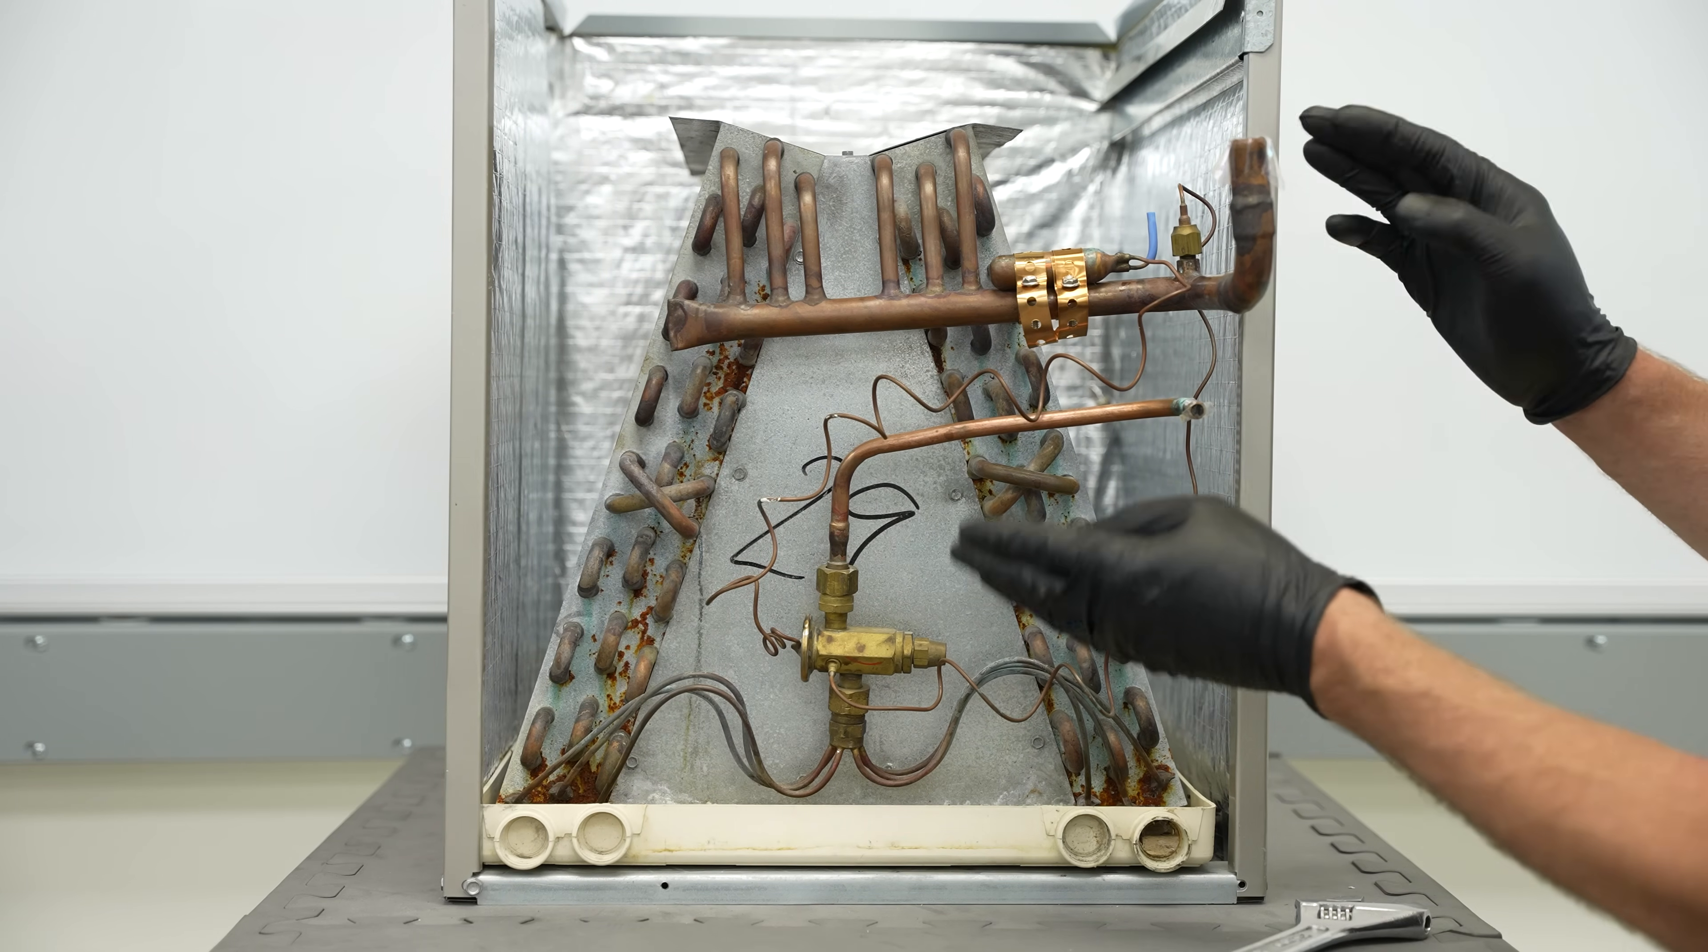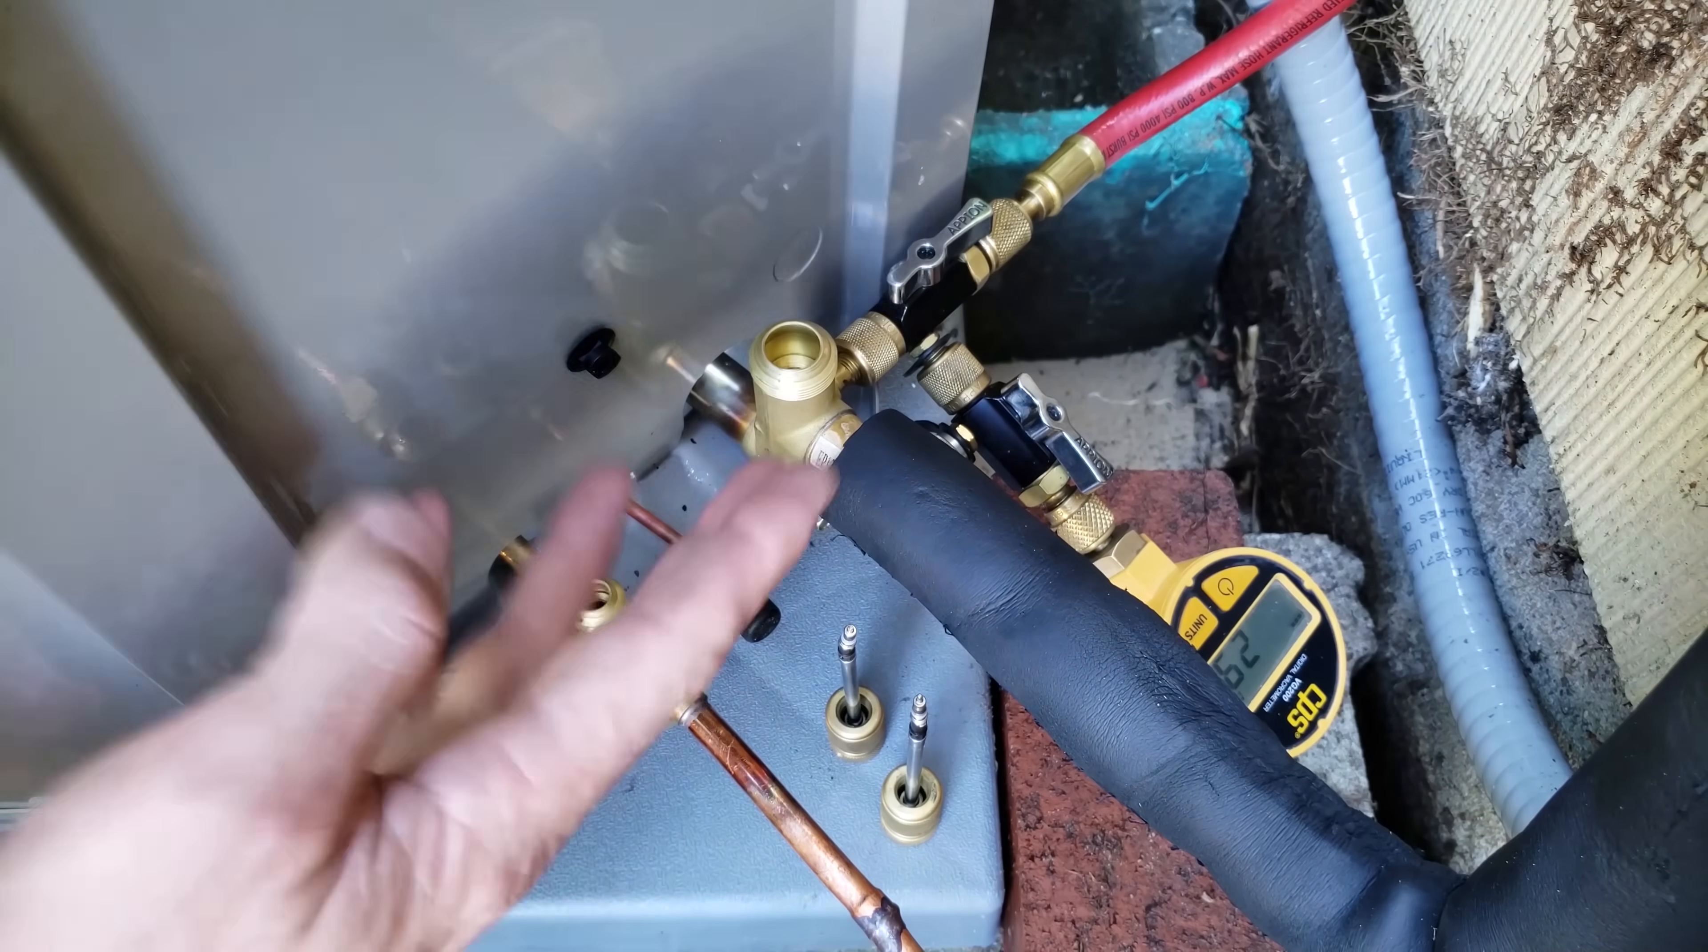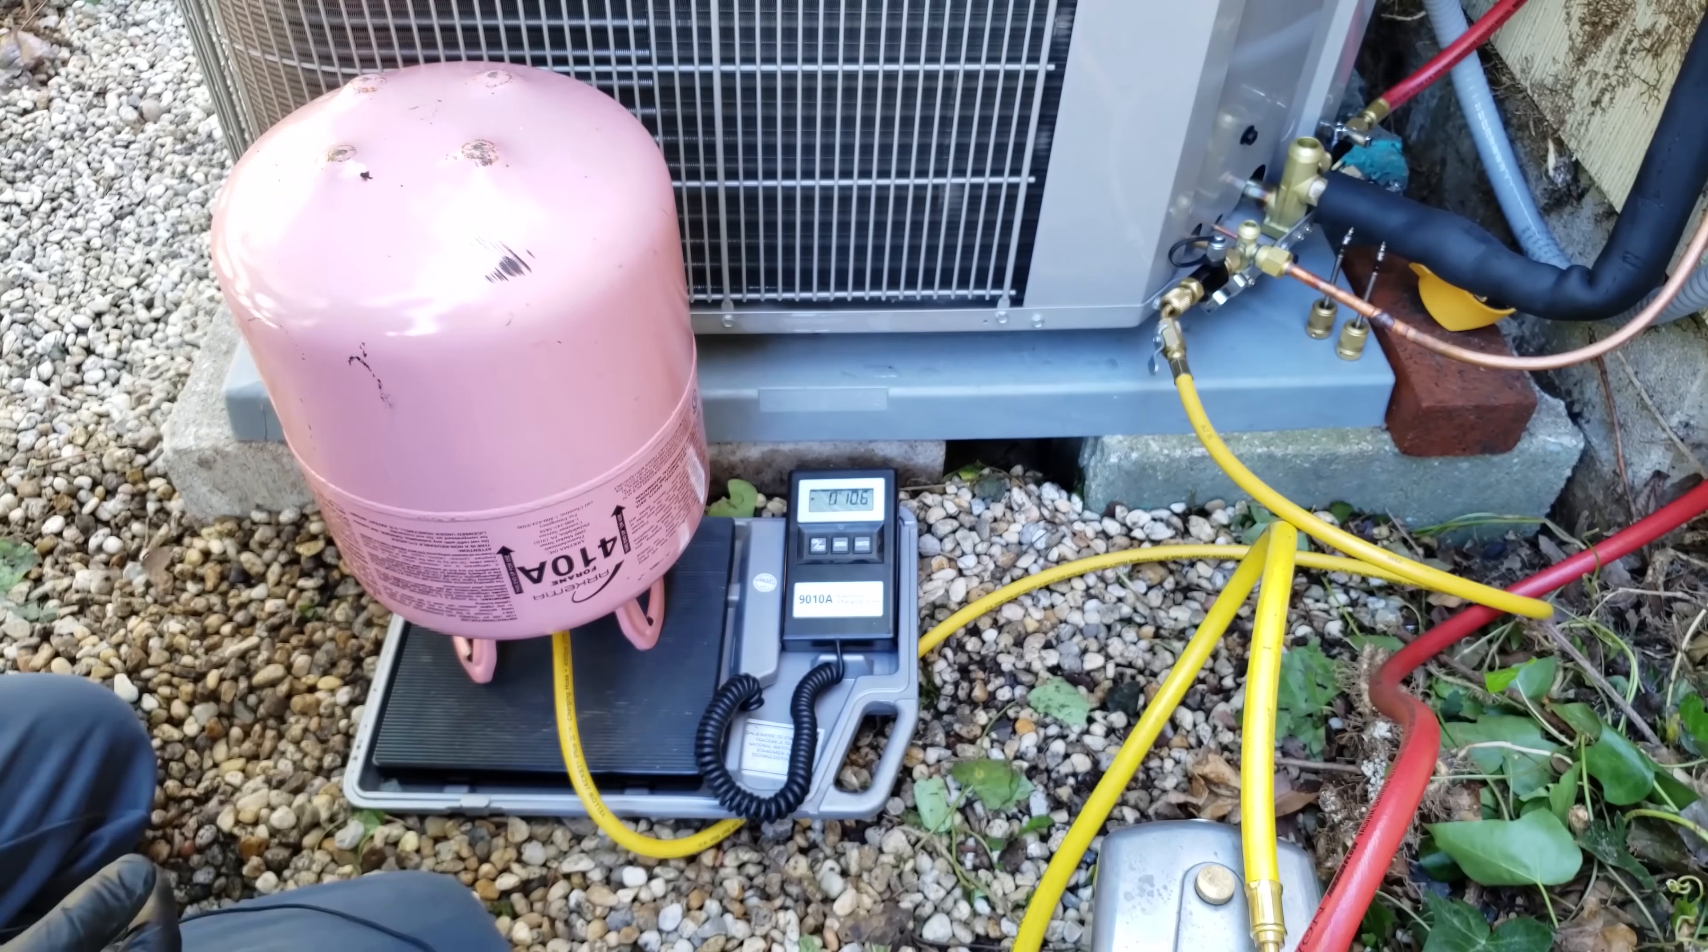After you put this together, you'd pressure test it, and then you would check the joints right here with bubble leak detector. After pressure testing, if you don't have any leaks, you can release the nitrogen, vacuum the system, and weigh in the correct amount of refrigerant back into the system. That would be the same amount of refrigerant that you recovered out.